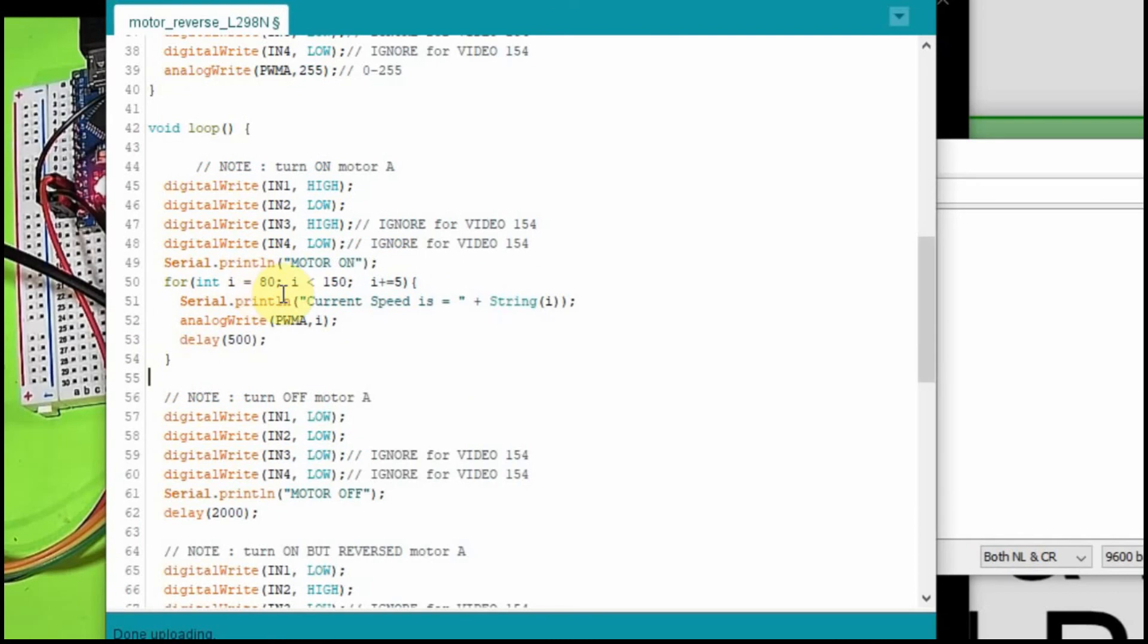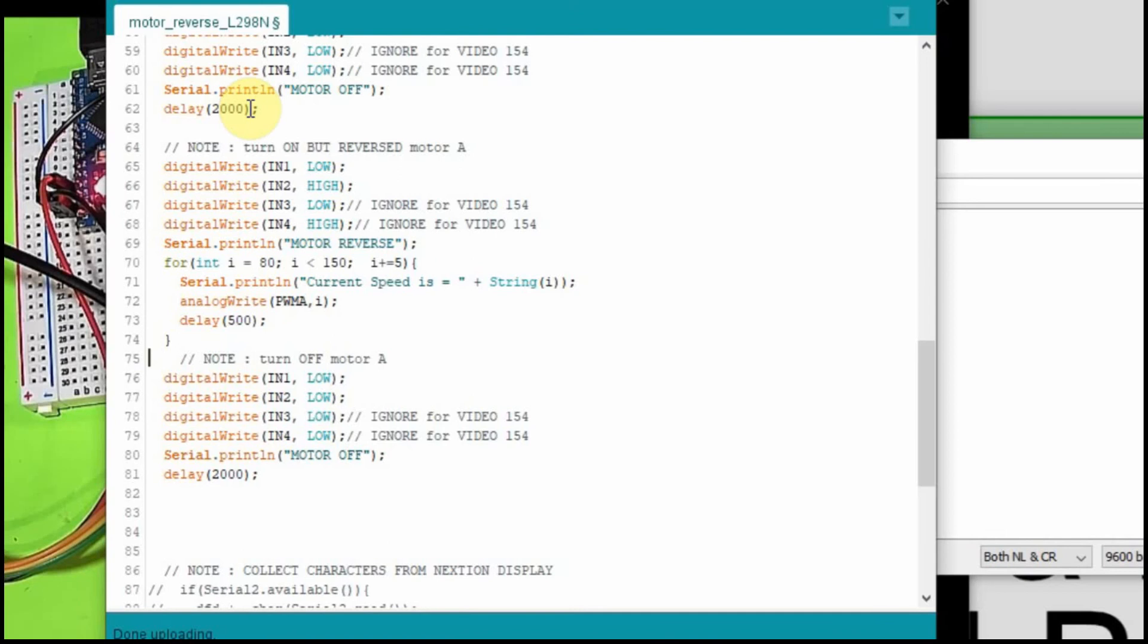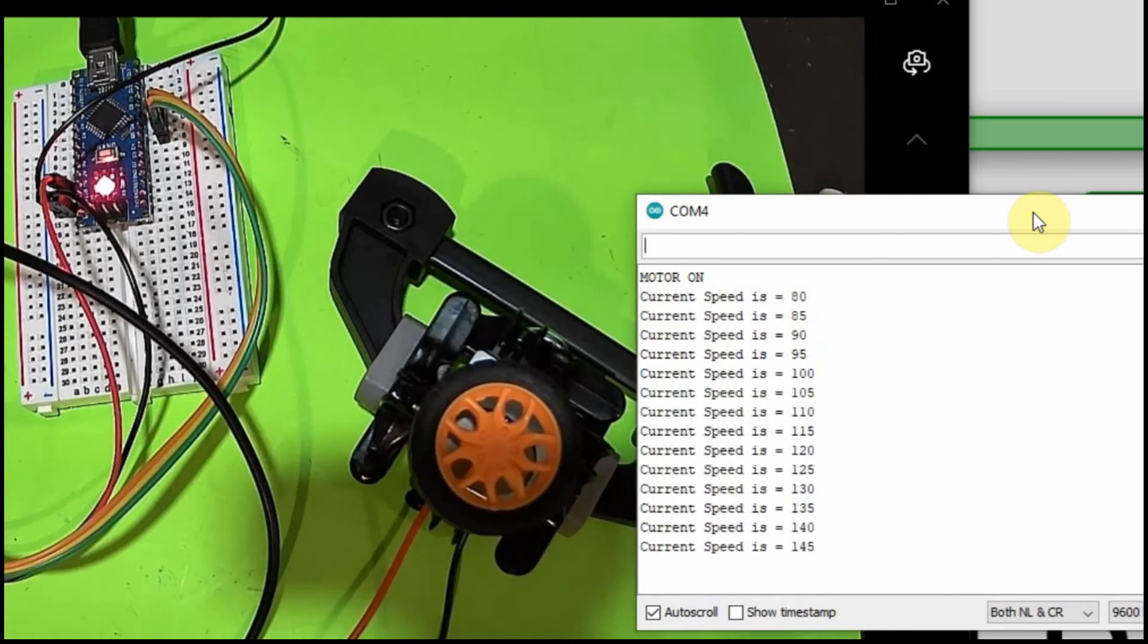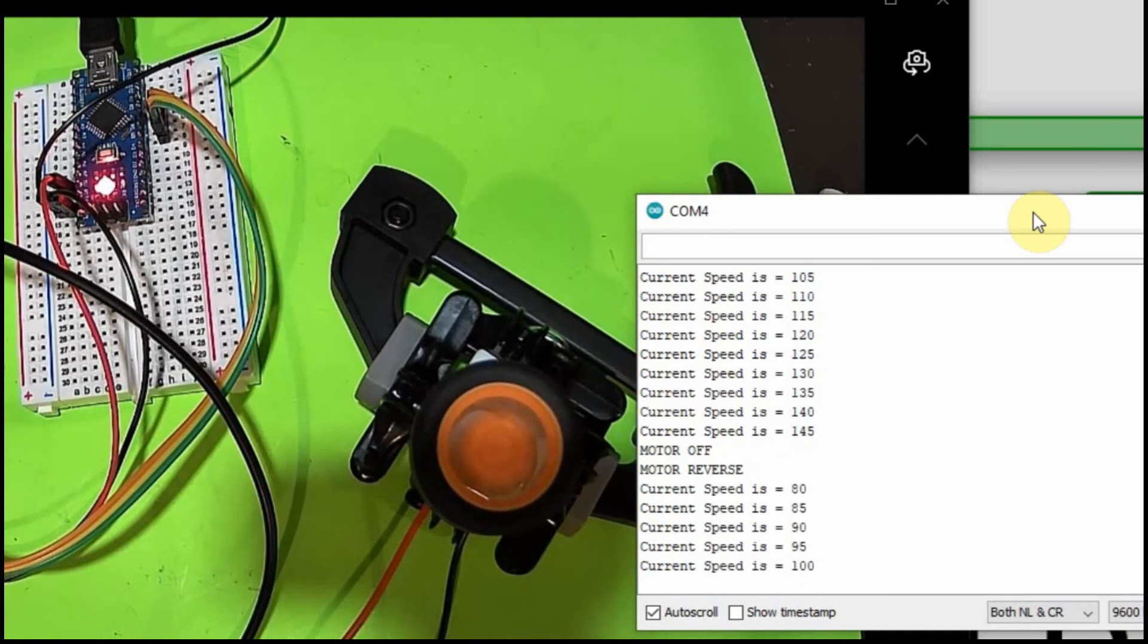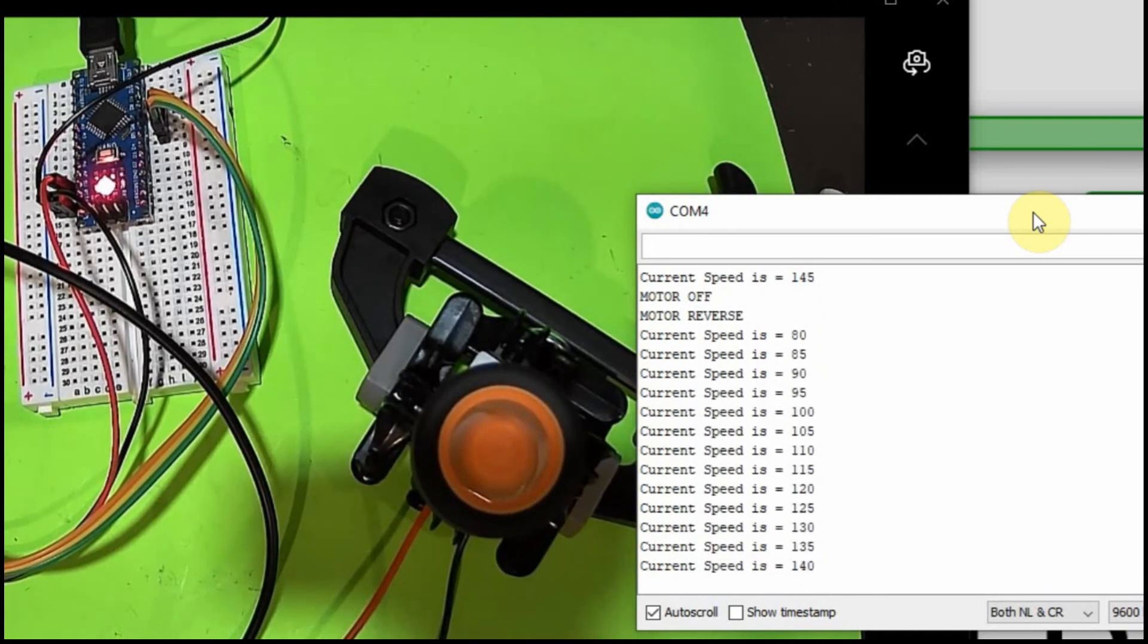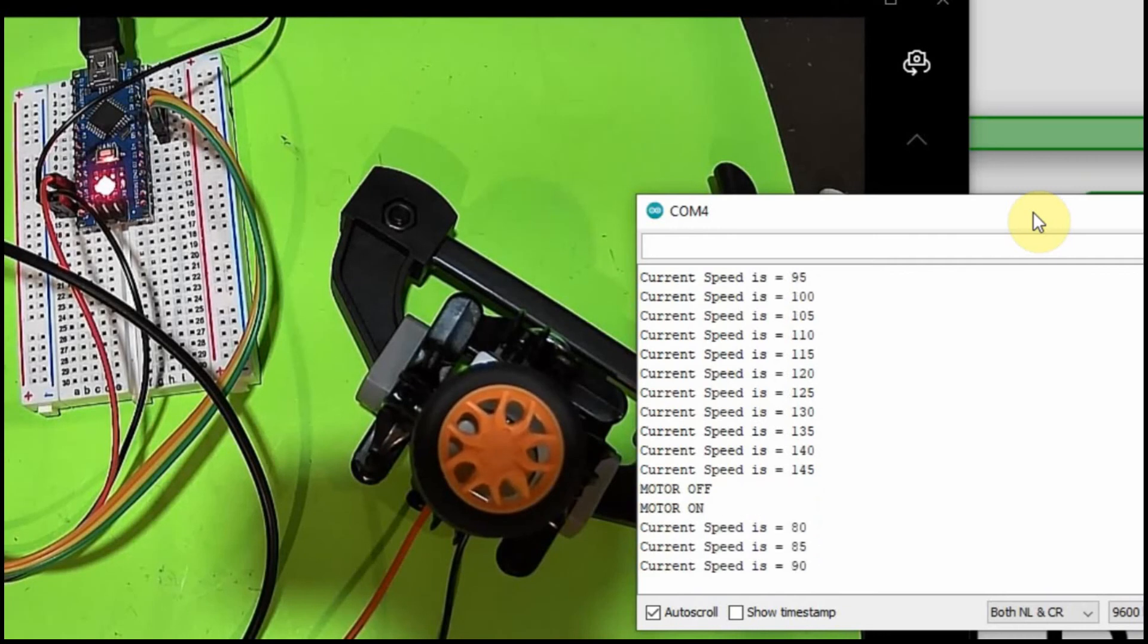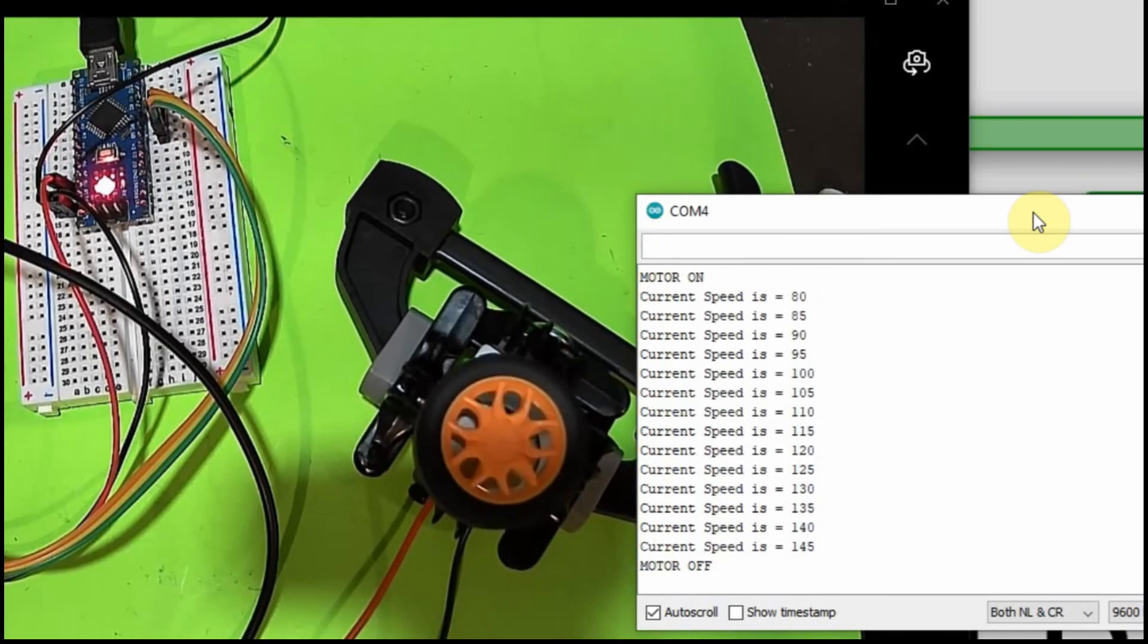So instead of going from zero to 250, we'll go from 80 to 150, and we're going to step in steps of five instead. So that'll give us a little bit more granular look at it. We're going to do the same thing on the reverse. What you'll notice is it doesn't act the same going both directions. Theoretically it does, but this is where a real world test comes in and shows you how things don't always work the way you think that they'll work. So it was about 95, 100? About what we thought. This is closer to 100 or 105. So they're pretty close, but they are just a little bit off.